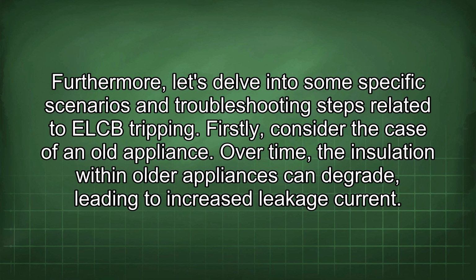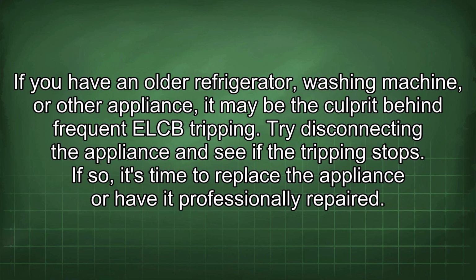Firstly, consider the case of an old appliance. Over time, the insulation within older appliances can degrade, leading to increased leakage current. If you have an older refrigerator, washing machine, or other appliance, it may be the culprit behind frequent ELCB tripping. Try disconnecting the appliance and see if the tripping stops. If so, it's time to replace the appliance or have it professionally repaired.